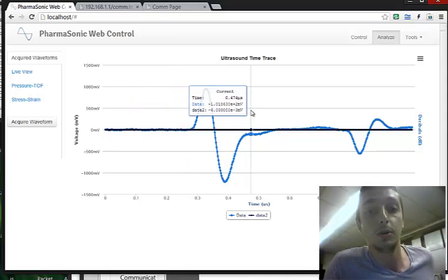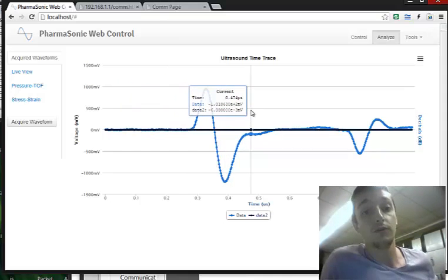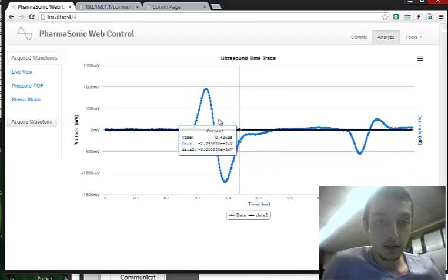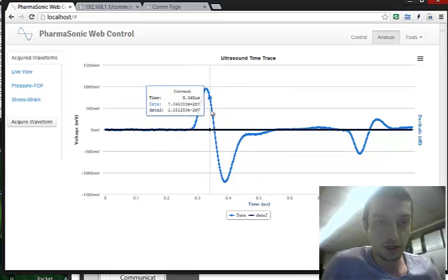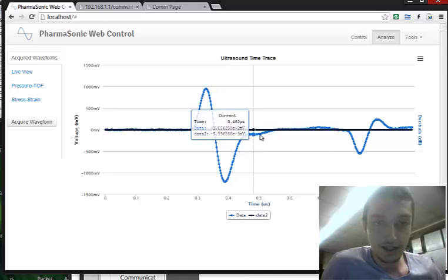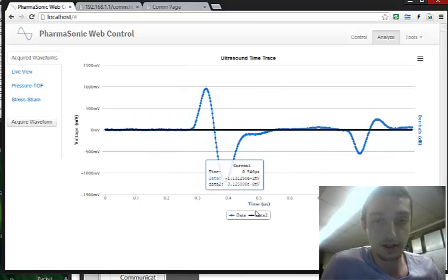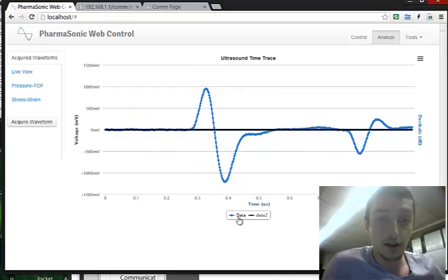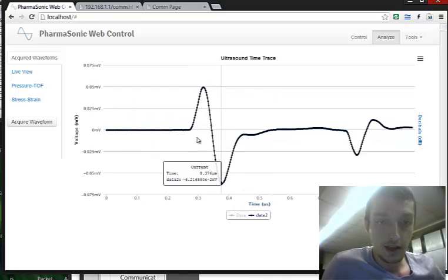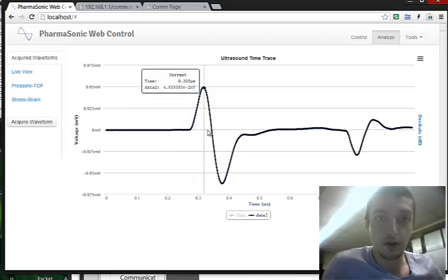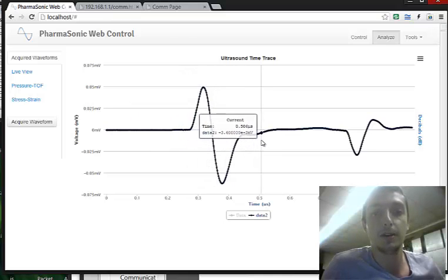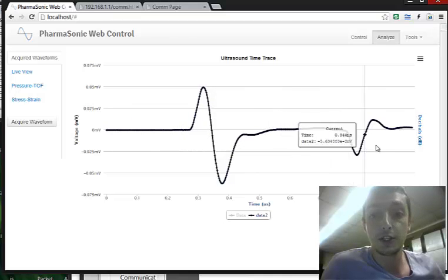In Catino's report, he said to use 400 volts, and here you can see the 400 volt response is a little jumpy, staticky at some points. Now I'm going to turn that off, and you see that at 100 volts it has the exact same shape, but it's much smoother.